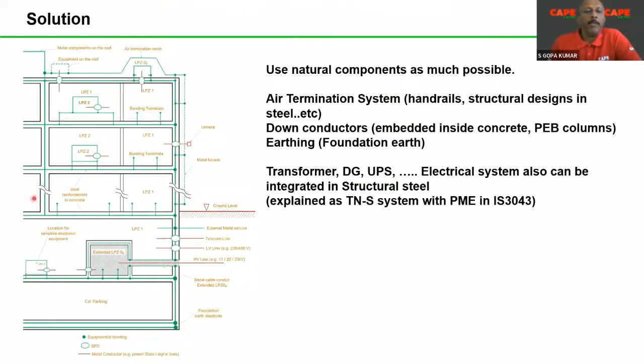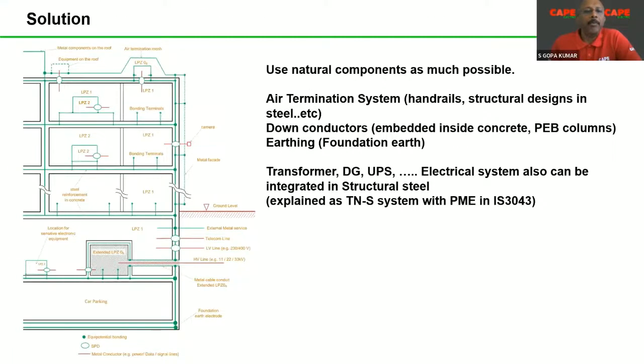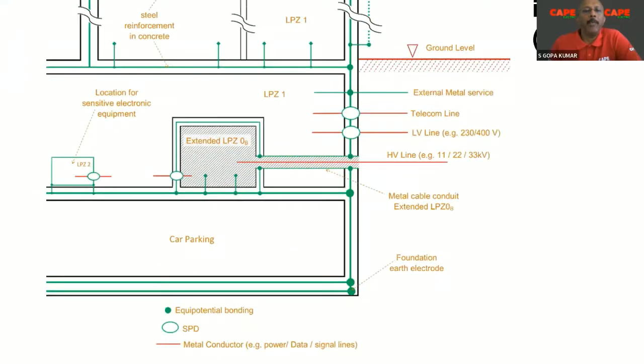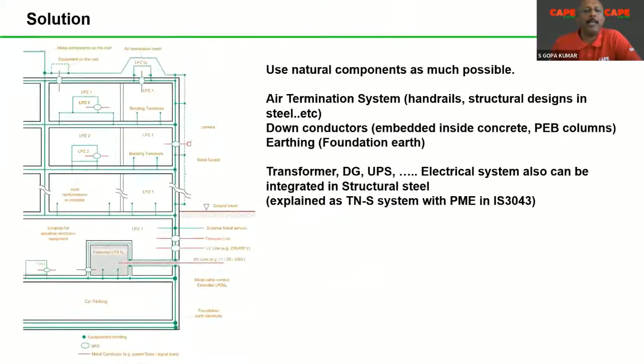This particular use of a natural component can also be used for applications such as transformer and DG. Our typical method is transformer neutral to earth electrode, transformer body to earth electrode, DG to earth electrode, UPS separate earth electrode, lift separate earth electrode, and so on. Actually, the methods we use for separate earthing of transformer, DG, UPS are, of course, a wrong method. The best and recommended method is to make use of the natural component, but please understand that the company or the person designing has to be skilled enough to make the design appropriately.